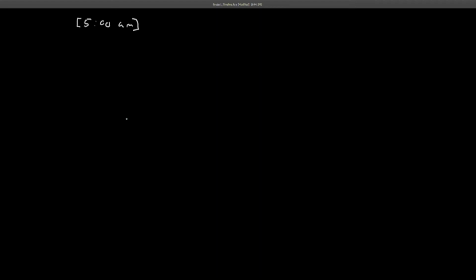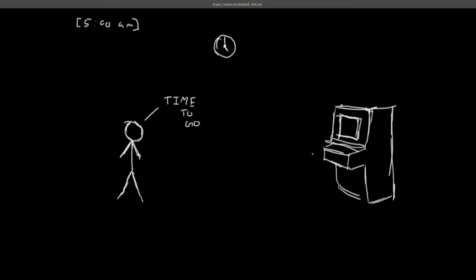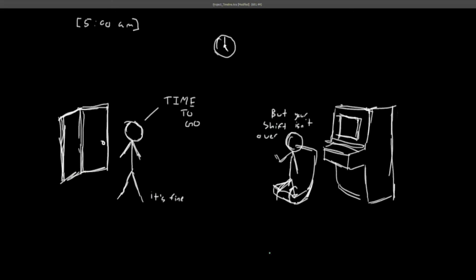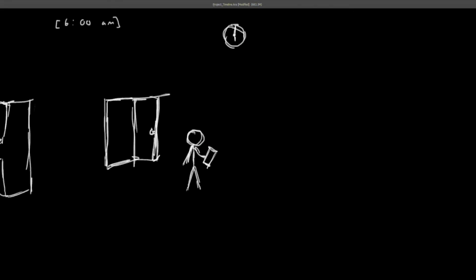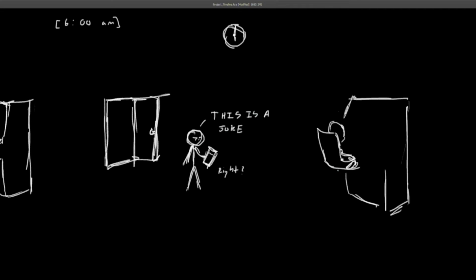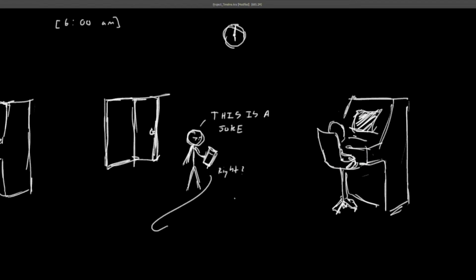5 a.m. Lead operator and satellite ISOM control room give briefing to Central Control Room, the CCR, and leaves to go home early. 6 a.m. New CCR operator arrives to start his 30th consecutive day doing 12-hour shifts. Shift log contained a 1-sentence logbook entry about the level and state of unit during startup that occurred early in the morning. Shift log entry read, ISOM unit, brought in some RAF to unit.